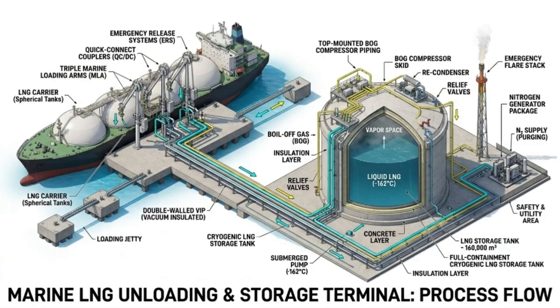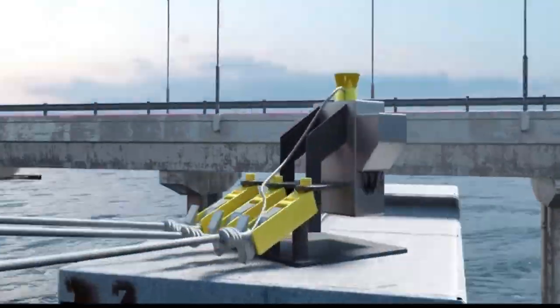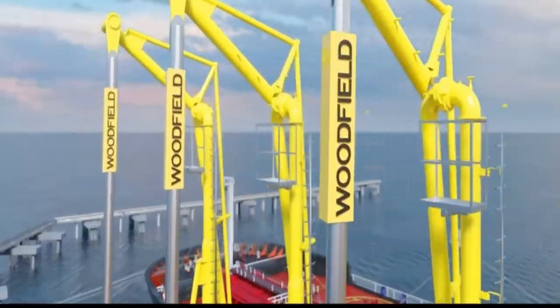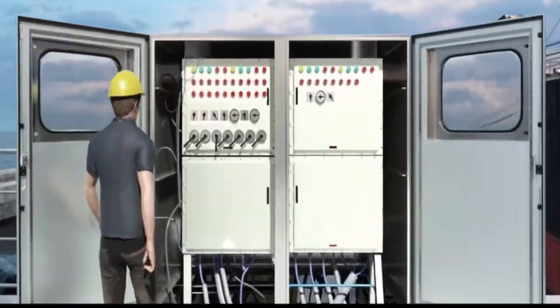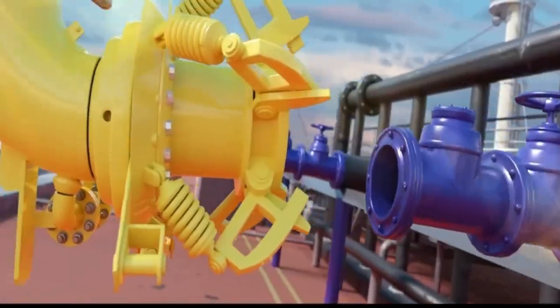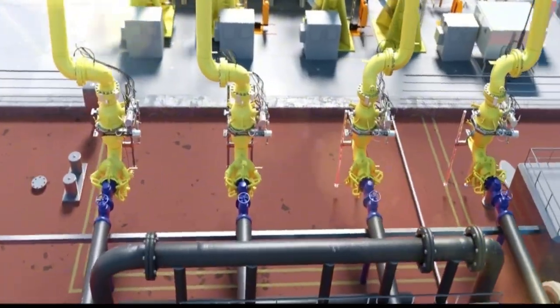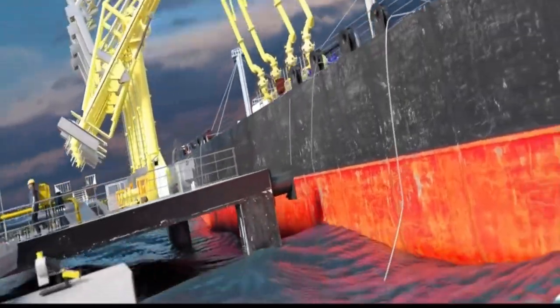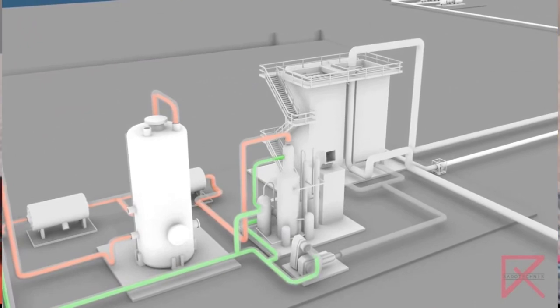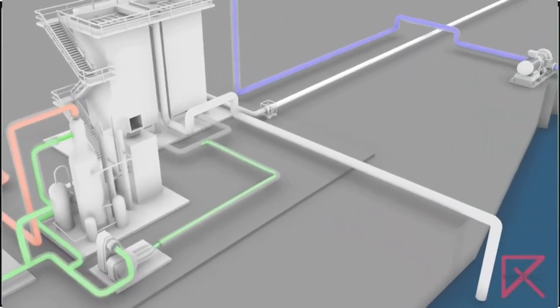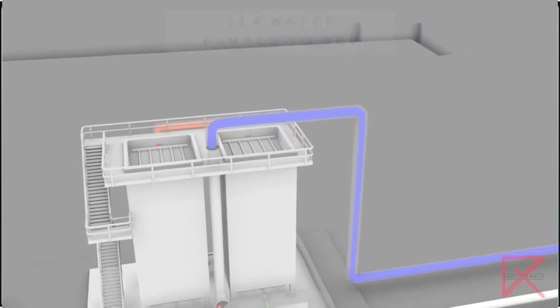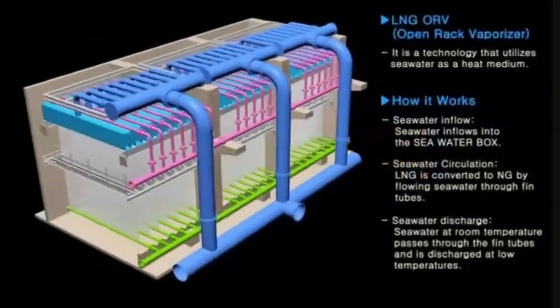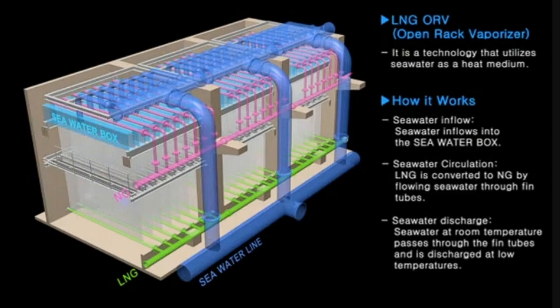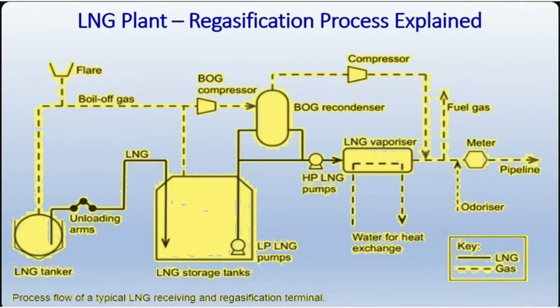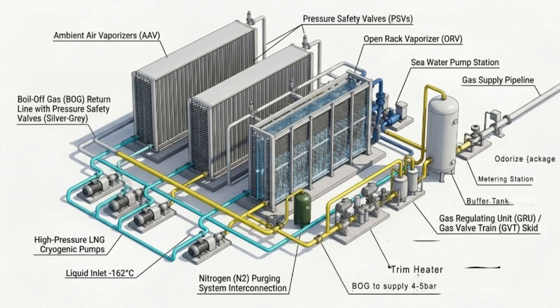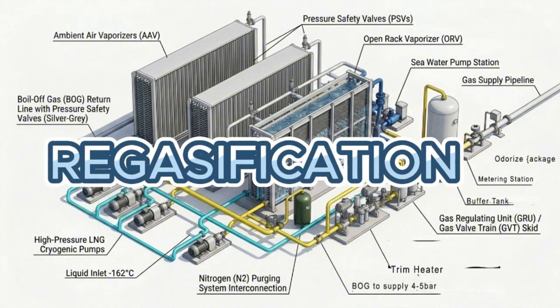This slide highlights the LNG receiving and regasification system at the plant boundary. At the jetty area, LNG is unloaded from carrier vessels through specialized marine loading arms, designed for safe cryogenic transfer at -162 degrees Celsius. The LNG is then stored and routed to the regasification system, where heat exchangers convert the liquid LNG back into gaseous form. During this process, the system controls gas temperature and pressure to ensure stable fuel conditions before the gas is delivered to the powerhouse. Next, let us move to the gas valve unit, the final safety and control stage before the fuel enters the engine.